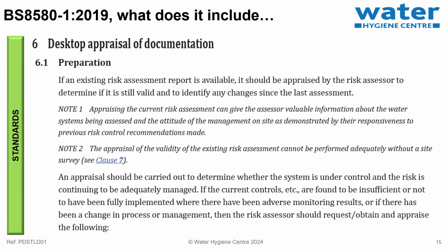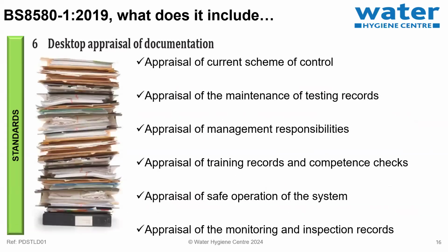And as long as you can get access to those things and they are readily available, they'll be happy. One of the most difficult things for a risk assessor to do is to get access to the documentation when they're on site. And this is really key because it's a desktop appraisal of how you're currently managing the risk. The condition survey that I mentioned earlier at the start is a look at the water systems, some temperatures and notes on status of condition. This is not a risk assessment. In order to assess the risk, you need to consider how the risk is currently being managed, and that is by having that desktop appraisal of the documentation completed as early as possible.